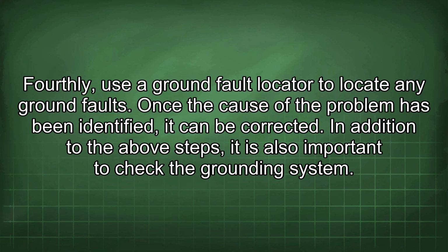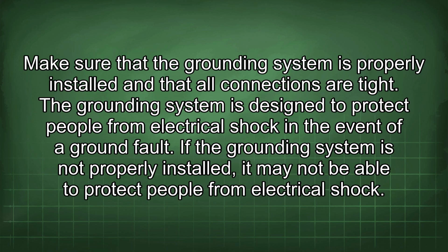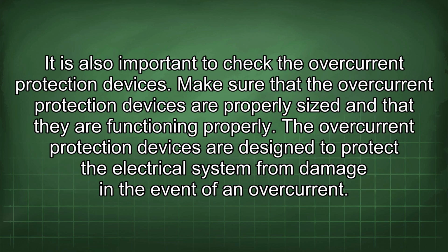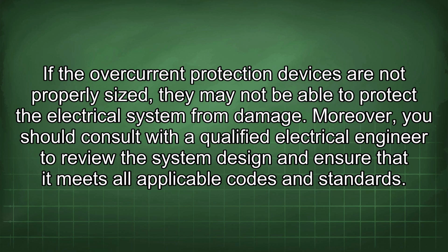In addition to the above steps, it is also important to check the grounding system. Make sure that the grounding system is properly installed and that all connections are tight. The grounding system is designed to protect people from electrical shock in the event of a ground fault. If the grounding system is not properly installed, it may not be able to protect people from electrical shock. It is also important to check the overcurrent protection devices. Make sure that the overcurrent protection devices are properly sized and that they are functioning properly. The overcurrent protection devices are designed to protect the electrical system from damage in the event of an overcurrent. If the overcurrent protection devices are not properly sized, they may not be able to protect the electrical system from damage.